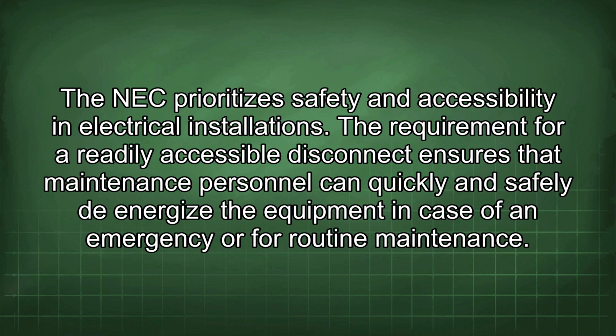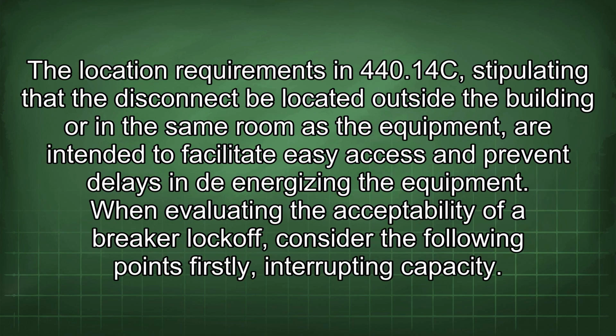The NEC prioritizes safety and accessibility in electrical installations. The requirement for a readily accessible disconnect ensures that maintenance personnel can quickly and safely de-energize the equipment in case of an emergency or for routine maintenance. The location requirements in 440.14(C), stipulating that the disconnect be located outside the building or in the same room as the equipment, are intended to facilitate easy access and prevent delays in de-energizing the equipment.